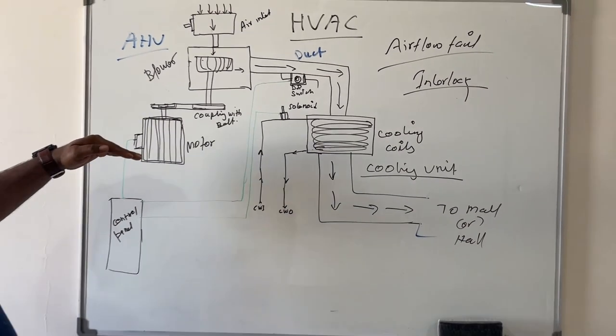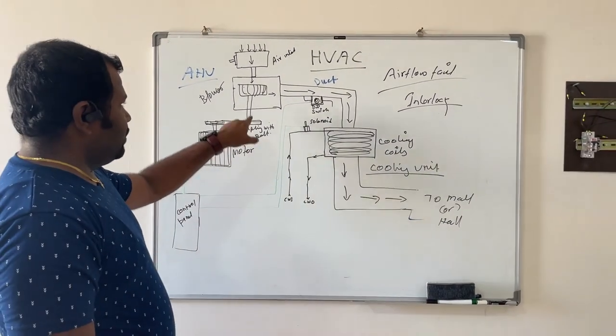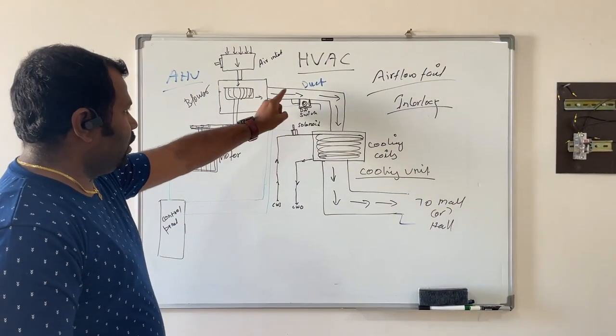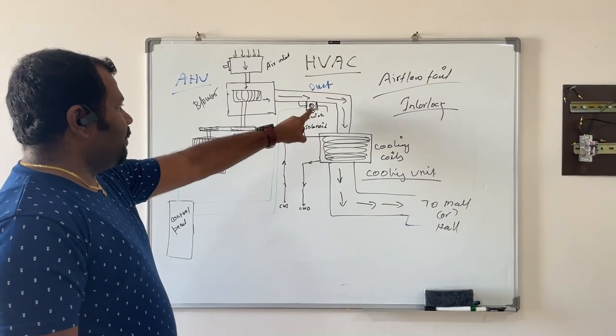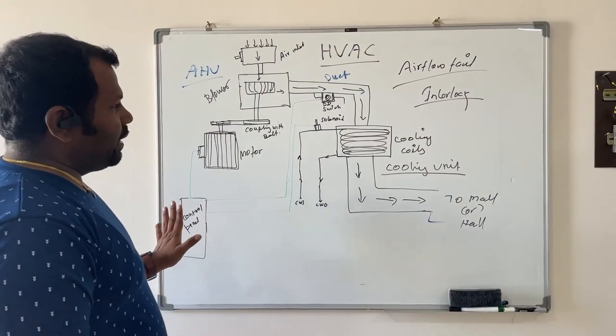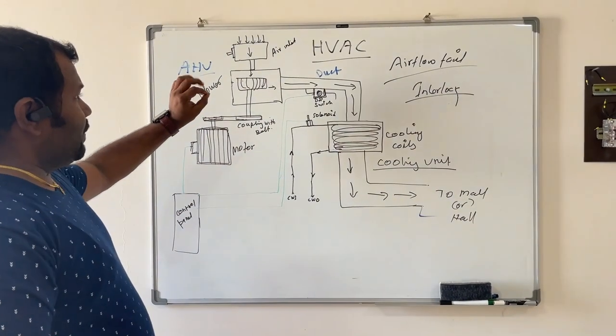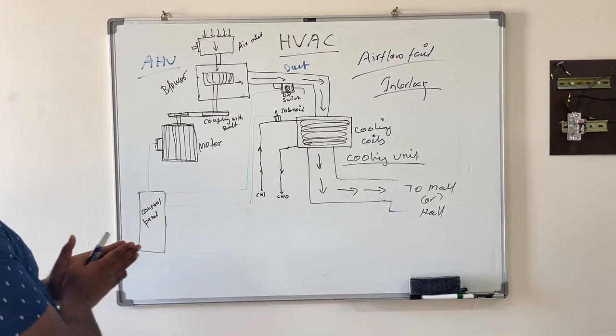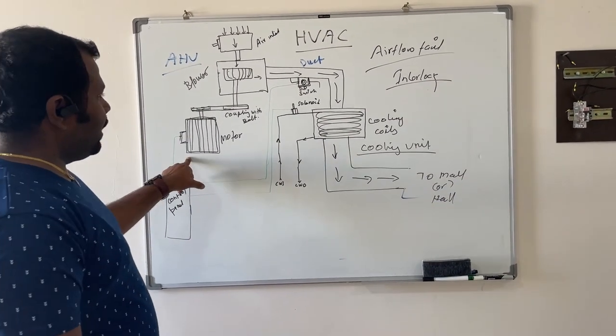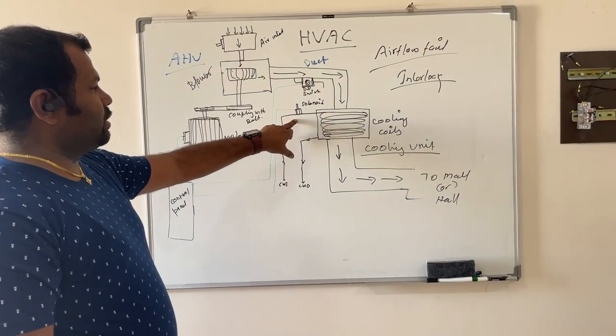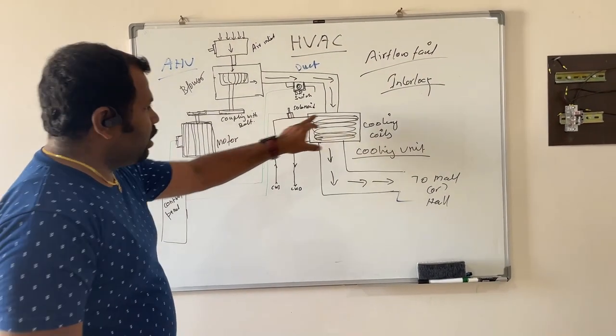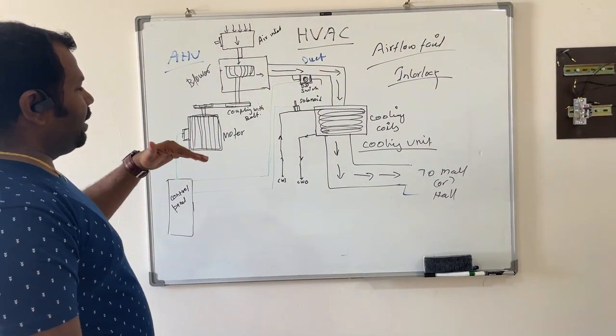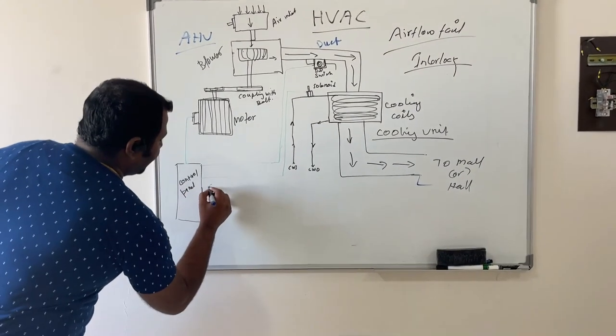When there is any electrical fault or mechanical failure, the blower will not throw the air through the duct. The DP switch will not detect any airflow through the micro switch and will send a signal to the control panel. The control panel will then stop the motor as well as close the solenoid coil which controls the cooling water and cooling gas through the cooling coils, so the AC will be completely stopped.